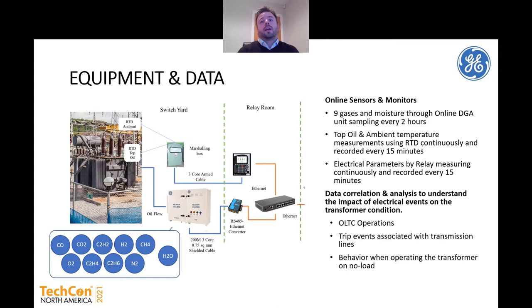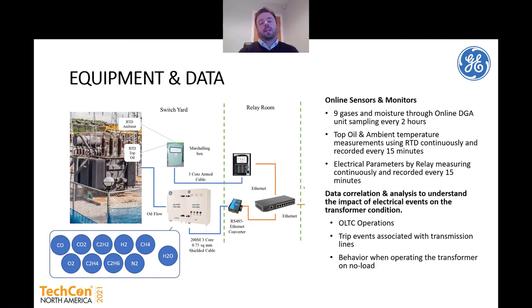There were a few online sensors attached to the transformer: a nine-gas-and-moisture online DGA taking a sample every two hours; RTDs doing continuous measurement of top oil and ambient temperature recorded every 15 minutes; and electrical parameters being recorded by the relay, measuring continuously and recording findings every 15 minutes. Data correlation analysis was required to understand the impact of electrical events on the transformer's condition — specifically the OLTC operations and whether tap position played any significant role in the gas generation being seen, as well as the trip events associated with the transmission line captured by the relay.